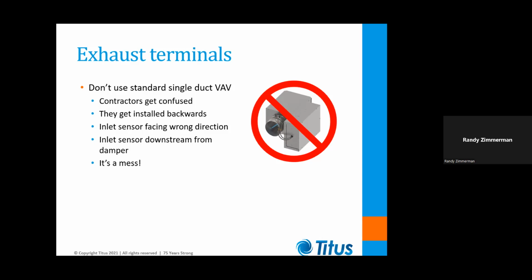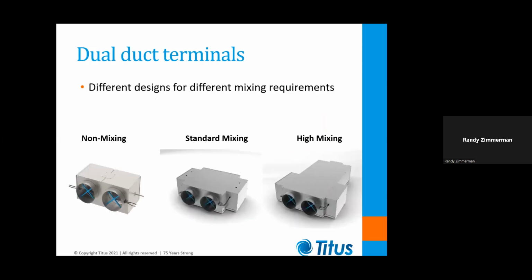And I will say that even if you install this box correctly with the inlet facing the room, that static pressure regain that the unit is designed to create in the supply mode will actually work against you in the exhaust mode and create more work for the exhaust fan to overcome. And then, of course, if you flip this box around backwards, you're creating a configuration that's very non-aerodynamic and will create a lot more noise and a lot more pressure drop than you would get from a standard exhaust box. So the best thing is just avoid it, use the correct exhaust box.